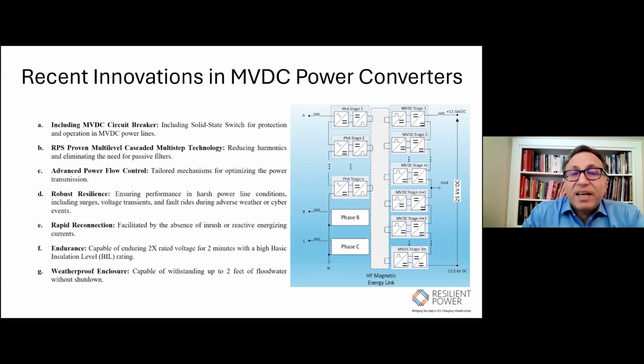But by cascading them, we can do a step conversion. We can turn them on in a step or staircase form, which is a multi-level power conversion, and it reduces the harmonics. All of these power modules in our technology are linked through a high frequency magnetic energy link. So we don't have any 60 hertz transformers. 60 hertz transformers are very bulky and use a lot of material, iron and copper, that has now been recognized as near-critical materials in the DOE roadmap.